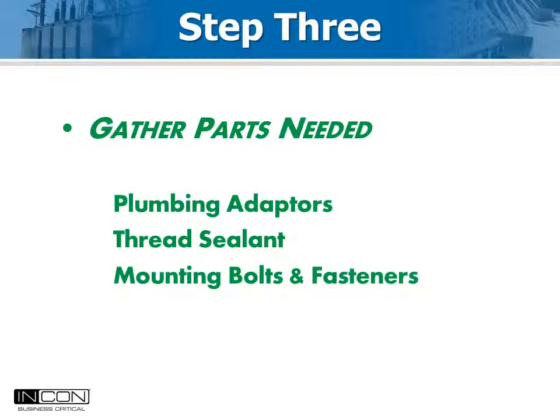The third step is to decide how you will connect the gas density sensor to the plumbing of the breaker. The sensor is always 3/8" British Standard parallel pipe thread. Typical connections available on Mitsubishi breakers are either 7/16" SAE or 3/8" British, like the sensor is. Fittings to adapt the sizes are available from Jobbers, McMaster, or convenient online vendors. When needed, Dow 111 silicone sealant is recommended for threads.